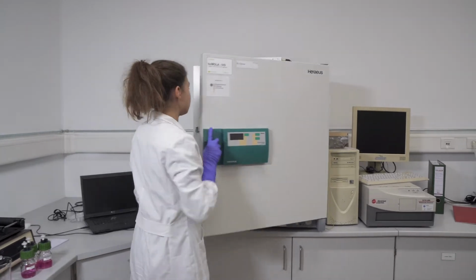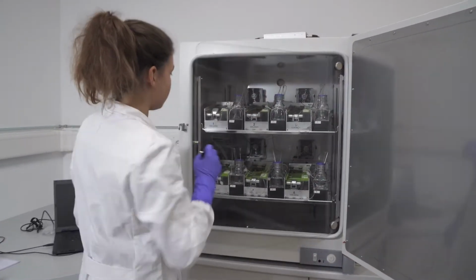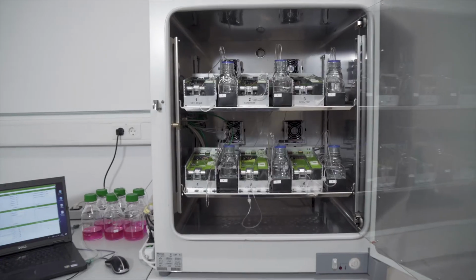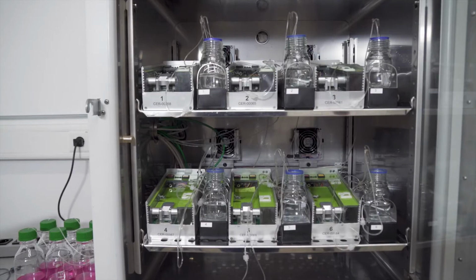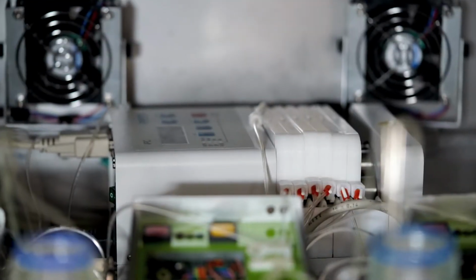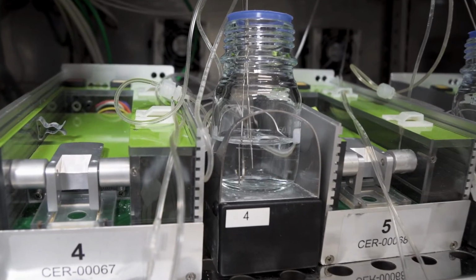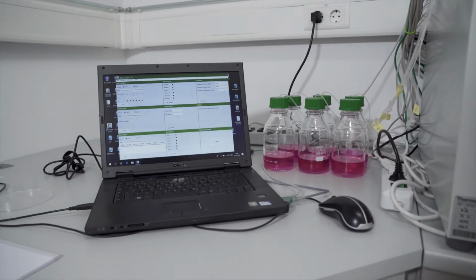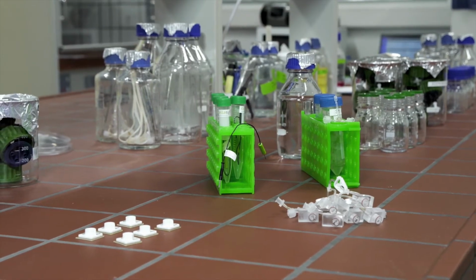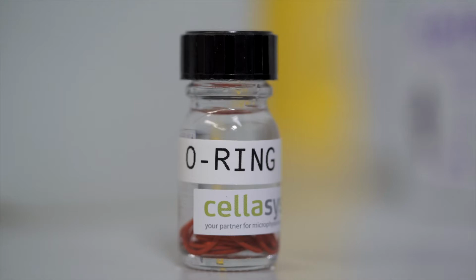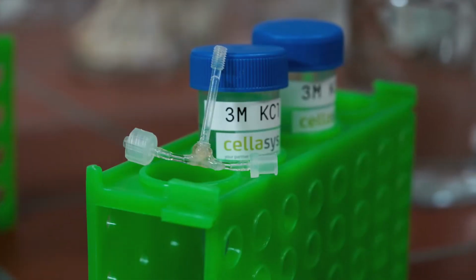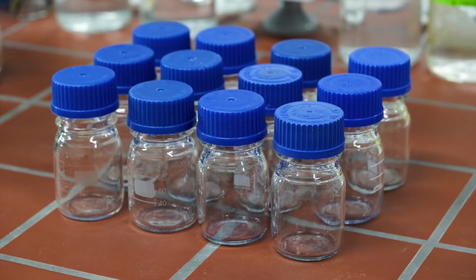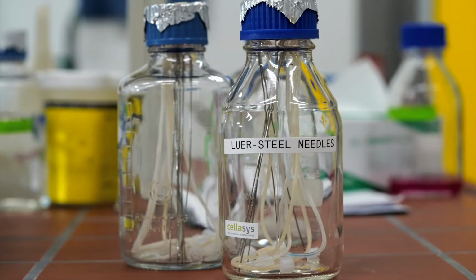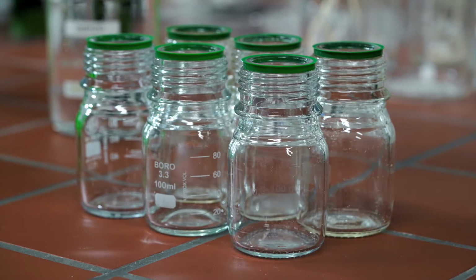The cellasys 8 assay is performed with the 6-channel emolla IVD bundle. The setup consists of a cell culture incubator for temperature control, 6 emolla devices, a peristaltic pump, 6 fluidic modules, and a laptop for control and data acquisition. Accessories required are 6 biochips with O-rings, 6 reference electrodes with barrels, 6 fluidic heads, 18 100 milliliter GL45 flasks with distribution caps and Luer steel needles, 6 flasks for sterilization and cleaning solutions.